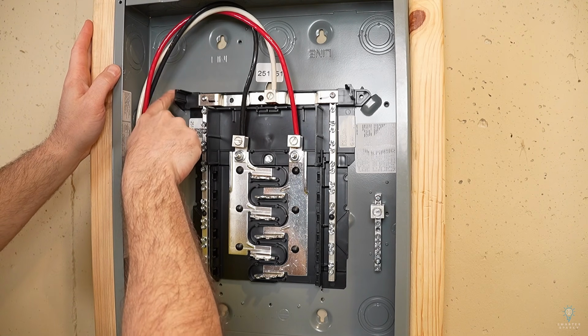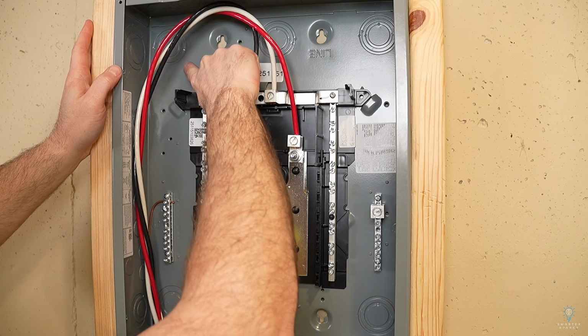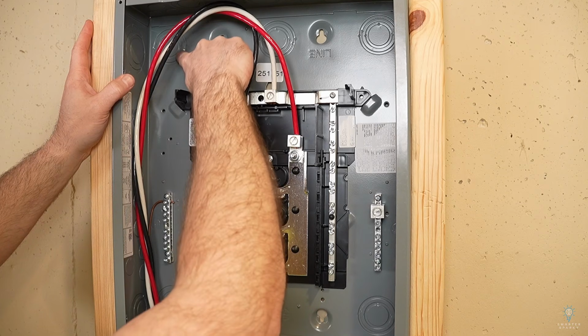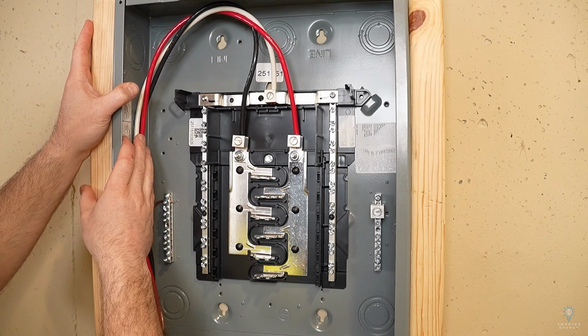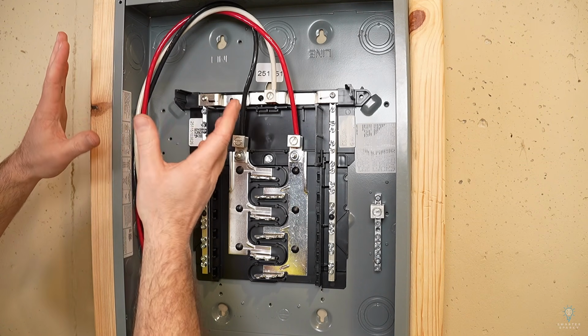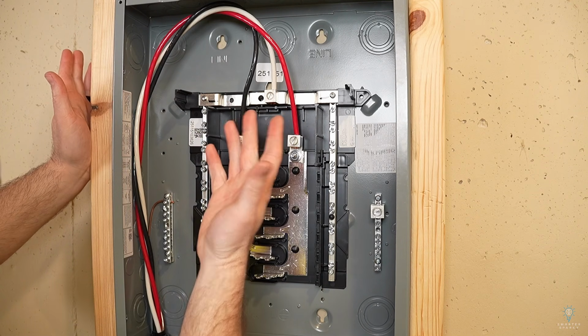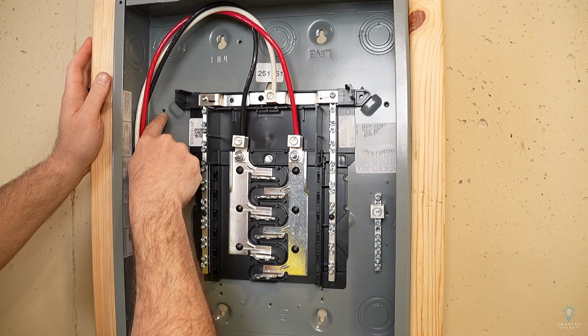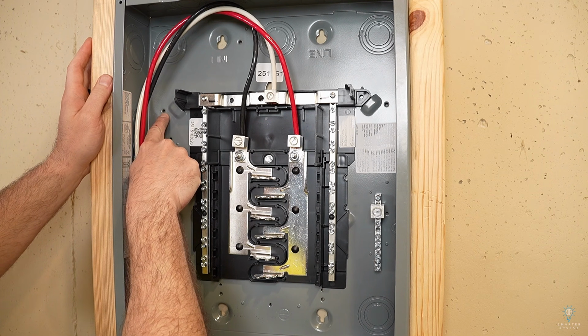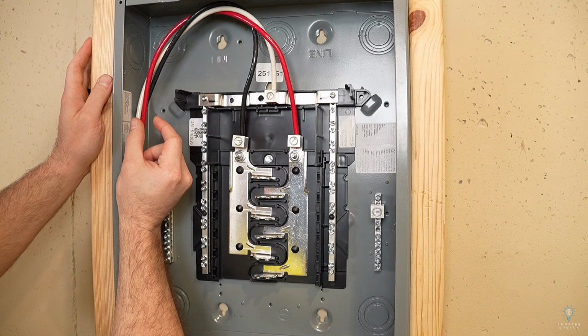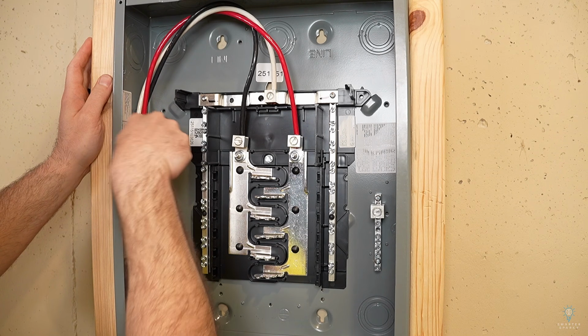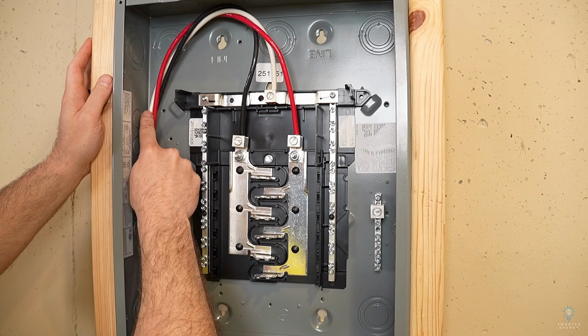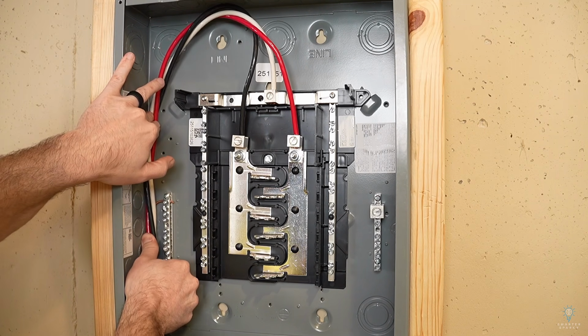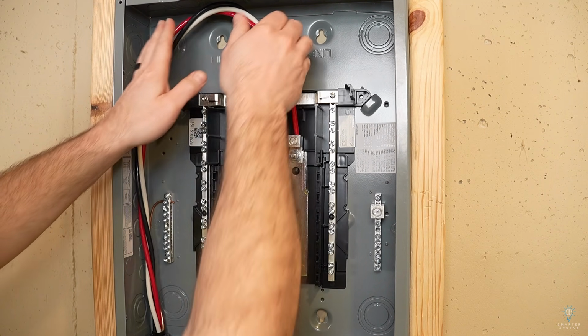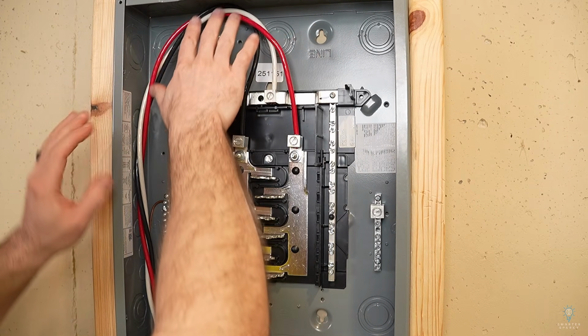I have seen some situations in which people will put those sticky back zip tie holders in the back of the panel. I've had a few inspectors get upset about that because they're not approved for inside of a panel. Other inspectors don't seem to care. Another option would be using one of these existing holes in the panel and getting those zip ties that have a hole in them so you can put a screw through that and pull those wires back as well.